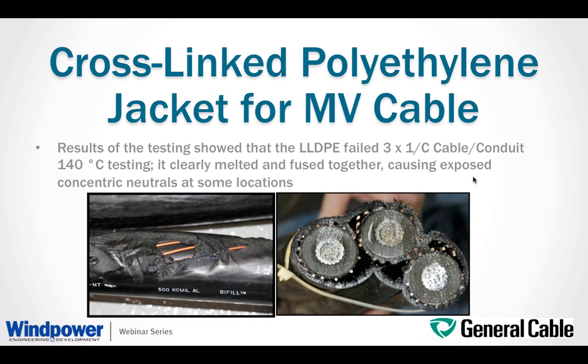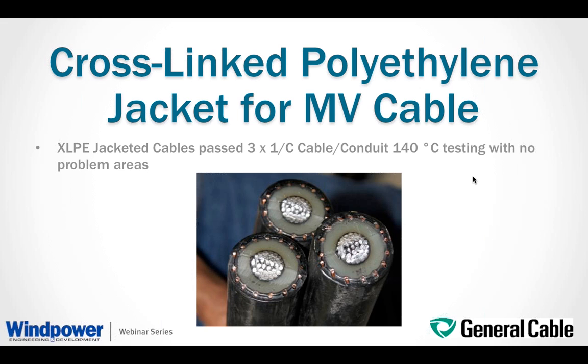Here are some pictures that show the results of the first testing completed with the thermoplastic LLDPE jacket. As you can easily see in the pictures, the jacket clearly exhibits melted spots, and on the trefoil construction the jacket is fused together, and in some areas it even caused exposed concentric neutrals. Then when you compare the testing on the XLPE jacketed cable, you can see that the cable maintains integrity and can easily pass that type of cyclic aging and thermomechanical test.